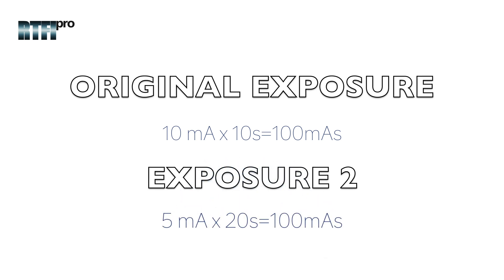Now let's review this example by reducing the milliampere by half and doubling the exposure time, which would be 5 MA and an exposure time of 20 seconds, equaling 100 milliampere seconds. Here, we reduced the original exposure milliampere from 10 to 5 MA, but doubled the exposure time from 10 to 20 seconds to produce the same 100 milliampere second exposure. As a result, the product of milliampere and exposure time have a direct proportional relationship with the quantity of x-rays produced.